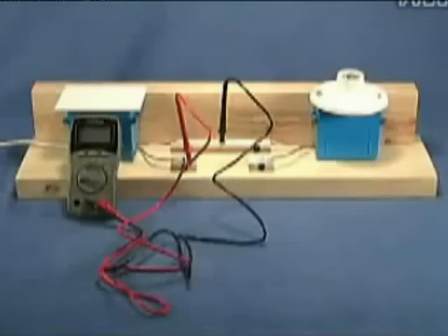We also need a multimeter to measure the voltage and current. However, it must be one that can measure AC voltage and AC current. To measure the voltage, we start with the device unplugged and the switch in the off position. We then place the multimeter in AC voltage mode and place the common probe in the neutral rail and the voltage probe in the hot rail, effectively putting it in parallel with the light socket. The device can then be plugged in.